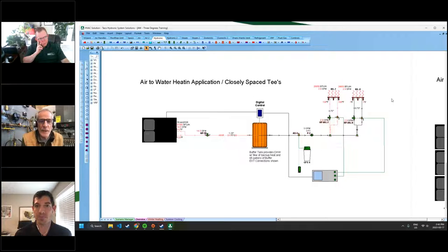And again, just a little piping change on that tank, and you could put your loads in parallel instead of series. Your loads are in series here. It's like the old Christmas tree lights. When you take one out, they all go out downstream of it. That's what happens when you put loads in series, is that second load is going to get a lower temperature than the first. If you want both to always have 120 degrees or whatever that shows there, then you need to put them in parallel, which you could do with the bottom header, and just a little piping change. And maybe we need to do a buffer tank seminar, because we could spend easily an hour on different ways to pipe these systems to maximize every one of them for every different application, is really what we would like to show.